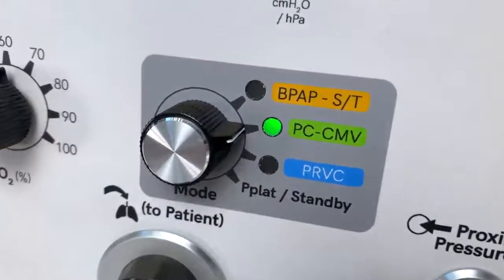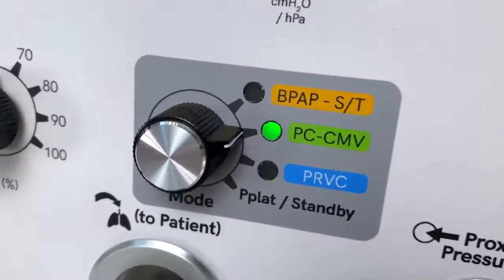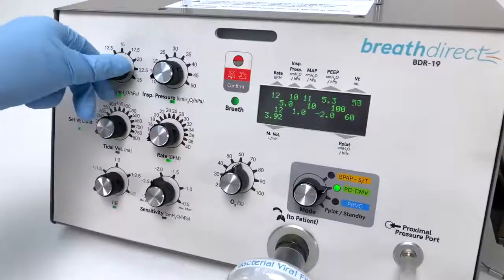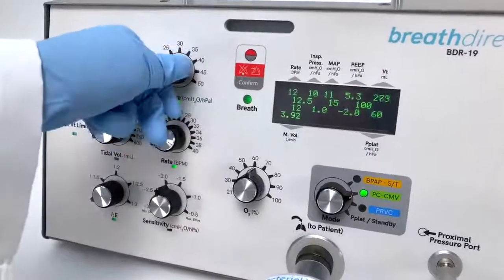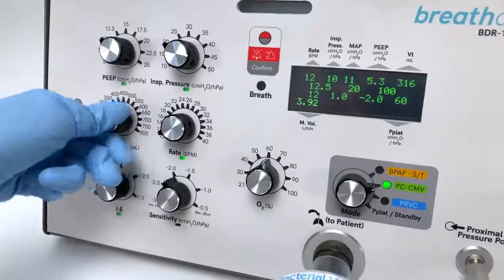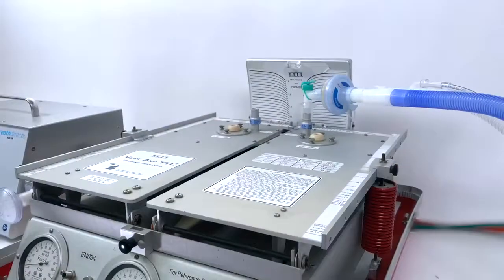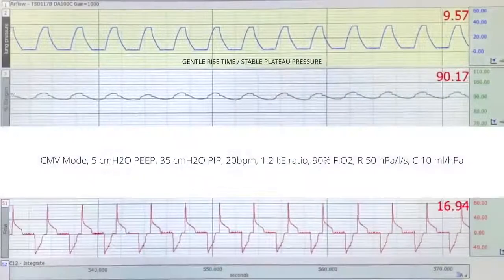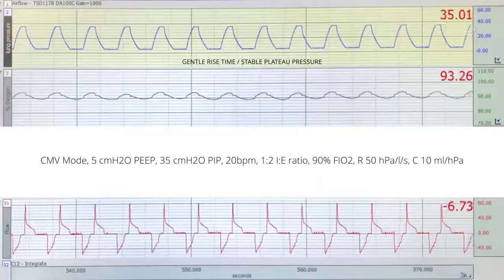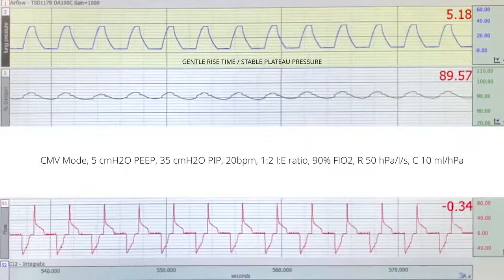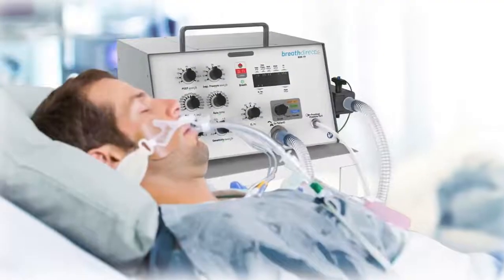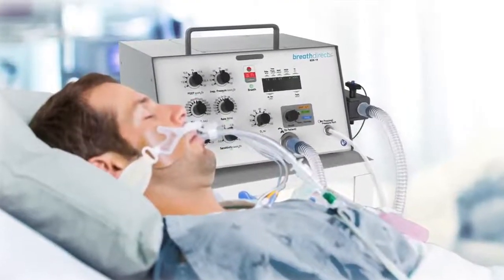CMV mode is a pressure-controlled mode that delivers mandatory breaths at the set inspiratory pressure, PEEP, rate, IE ratio, FiO2, and high and low tidal volume alarm limits. Breath delivery results in a smooth lung pressure waveform, with a gentle rise time and a stable plateau pressure, without overshoots or undershoots. CMV mode can be used when the patient is dependent on mechanical ventilation.